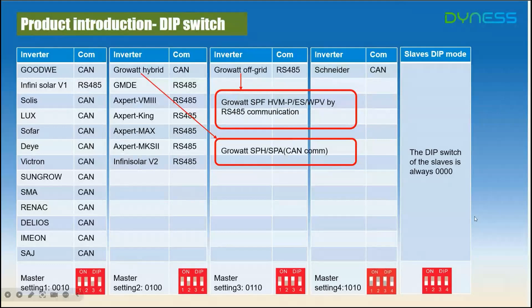And if you do a parallel setup, you need to set the dip switch like this. Also, when you change the dip switch, you need to power off the BMS, power off the battery, and restart. Otherwise, the setting will be invalid. Okay, this is about the dip switch.